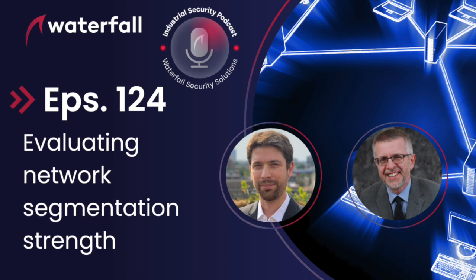17 3-foot by 5-foot as-built network diagrams, big, massive things full of wiring diagrams. And he's paging through these things one after another. And he looks up and he says, you realize there's a path from the internet into your deepest control system here without ever passing through a firewall, just routers. What do you mean? Well, on this network diagram, it starts here from the internet, and then you go to this machine and that machine through here, and then you take this thing over here that is kind of off in the corner, takes you over to this page, bang, bang, bang, you're in. And the reaction was, give me that, snatch the network diagrams back, kick us out, go and fix the problem, and bring us back in a couple of months.